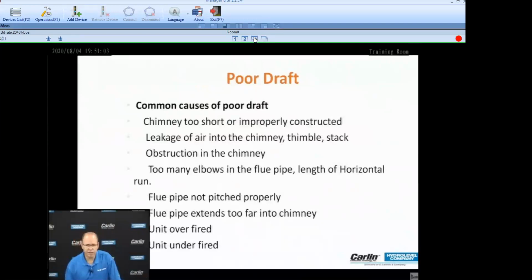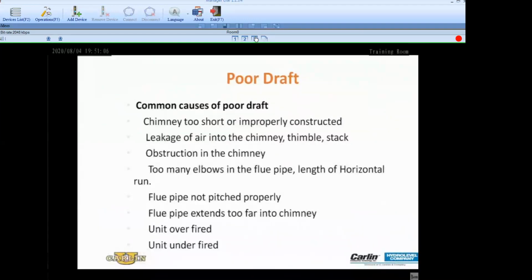Common causes of poor draft. You know, there's quite a few. Cold air leaking into the chimney, flue gas temperature not high enough, too many elbows, too much pipe. If it's an outside chimney and it's not lined and your appliance is putting out very low flue gas temperatures, well, you're going to condense. I've seen buckets, not necessarily on oil-fired appliances, but on gas. I've seen buckets in the basement underneath that last elbow to collect all the condensation that drips out of that elbow. Instead of dripping onto the basement floor, it drips into a bucket. Why? What causes that?